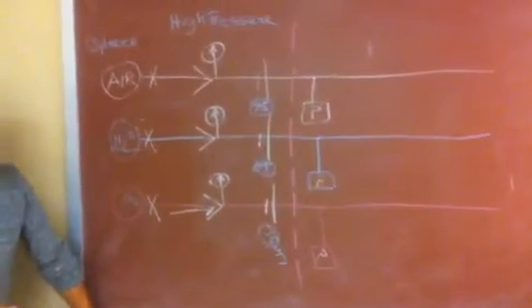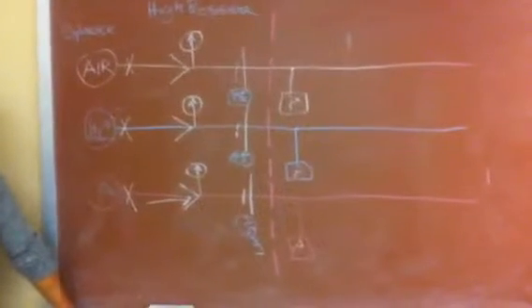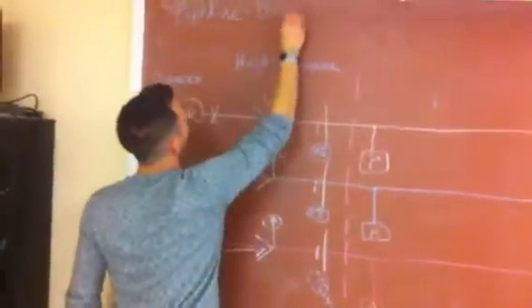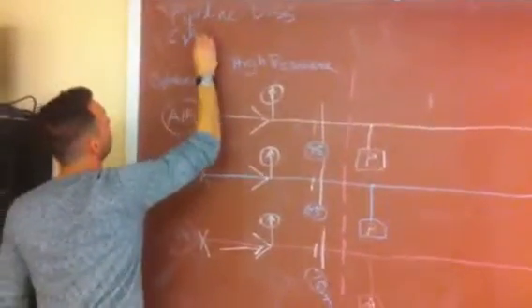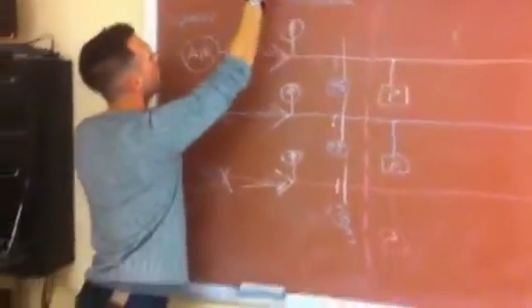So, also, this system, very good. And that's the diameter. Diameter index safety system. It's just like the PISS system, but for the pipeline. And it's just diameter, and you use a diameter instead of a pin. It's diameter. Yeah, it's big. How big is it? So we'll say oxygen is maybe the biggest one or something like that.